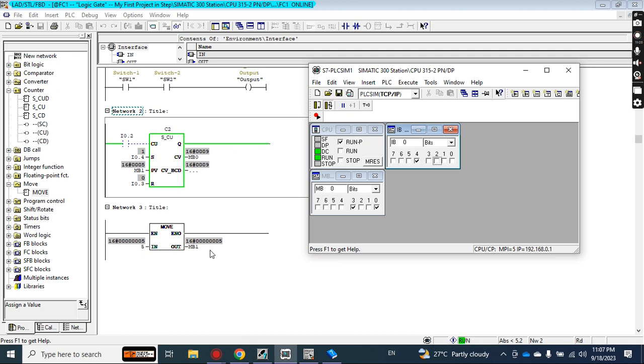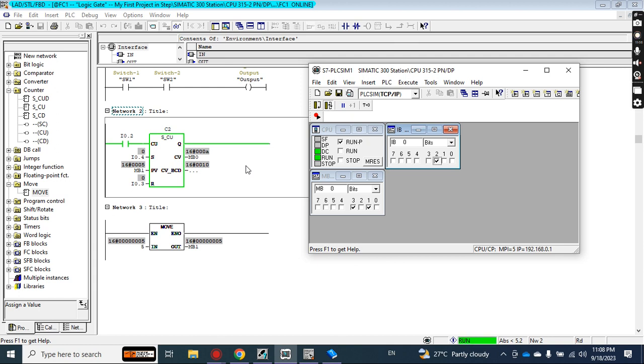To reinitialize the counter to the preset value stored in MB1, provide a pulse at I 0.4 — the value becomes 5 again. Give more pulses and it continues counting onward. You will also notice two values displayed: one in decimal and one in hexadecimal — for example, 10 in decimal is 'a' in hex, 11 is 'b', 12 is 'c', and so on.